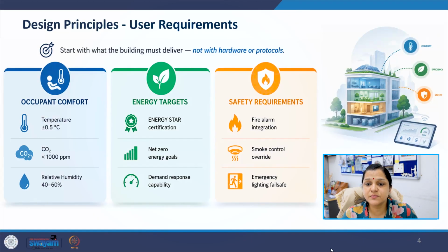Similarly, energy goals must also be defined clearly. For example, the building may target Energy Star certification or net zero energy operation. Demand response capability may also be required. Safety requirements are equally important. The BAS may need integration with fire alarms, smoke control systems, and emergency lighting systems. The key lesson is this: a building automation system must be designed around performance objectives, not around equipment category.